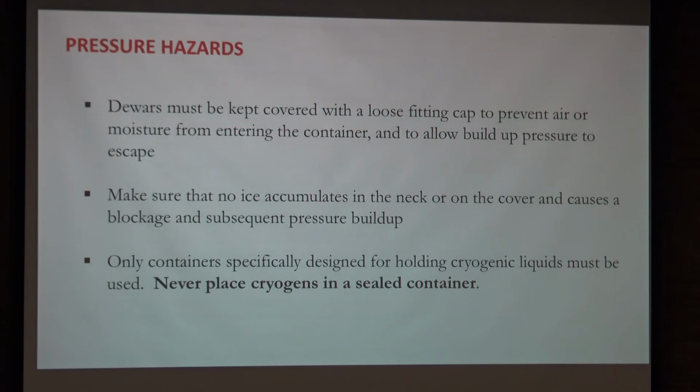And once your dewar has high pressure, it will essentially turn into a bomb and present a hazard in its own right. We have had this in our department. So if you have these open dewars, you want to keep them capped off with a loose-fitting styrofoam cap that will protect you from splashing cryogen, but will also not allow any pressure buildup. That will essentially come off easily if the pressure inside builds up too much.